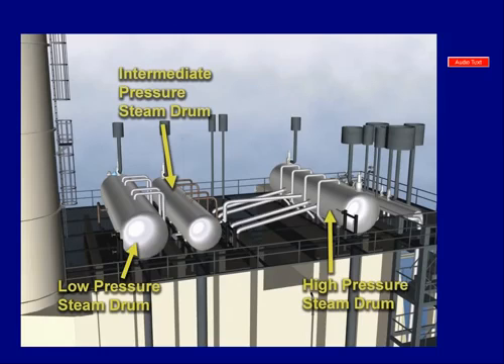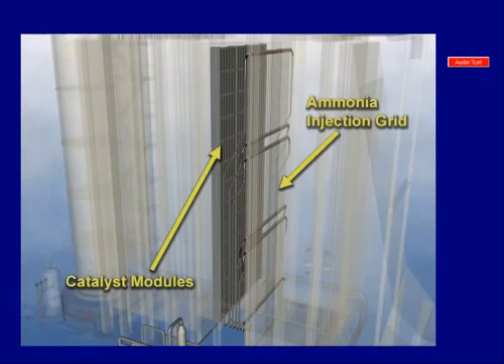The three pressures are called high, intermediate, and low pressure. These terms correspond to the classification of steam pressures they produce. The HRSG uses three steam drums of similar design to heat water, convert water into steam, and then superheats that steam in additional tubing designed for that purpose.